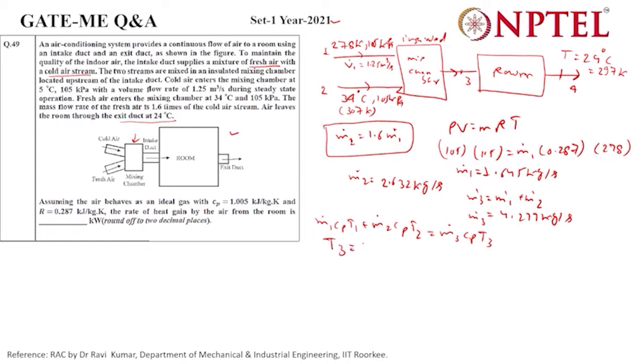When we calculate T3, it becomes 295.85 Kelvin, and if we want to convert to degrees Celsius, it becomes 22.85 degrees Celsius. This is the temperature at the exit of the chamber. This air is going to the room, so when it exits the room it will become 24 degrees.